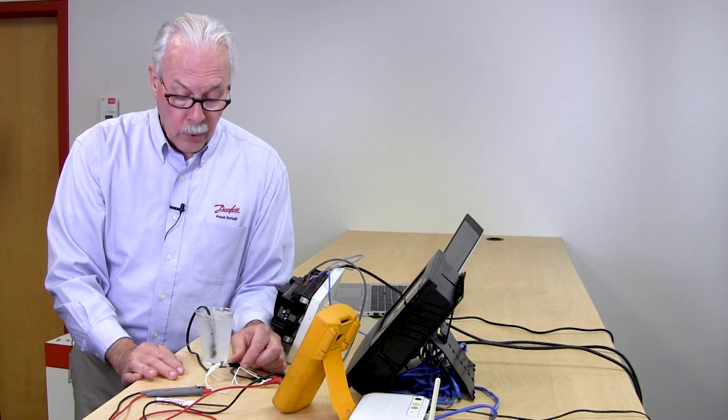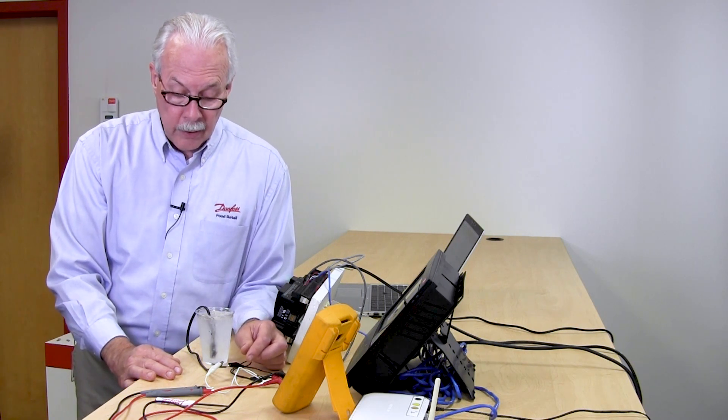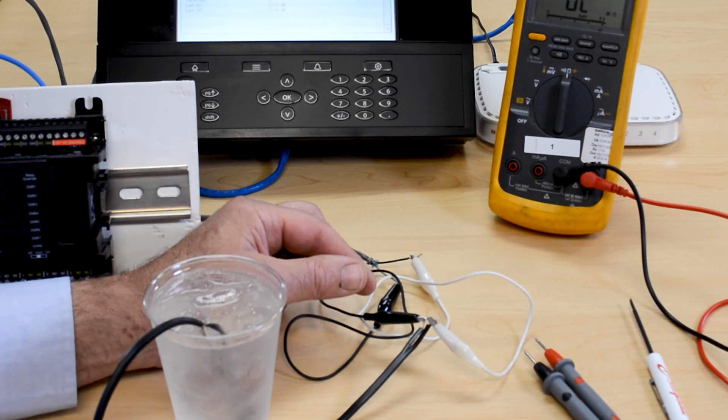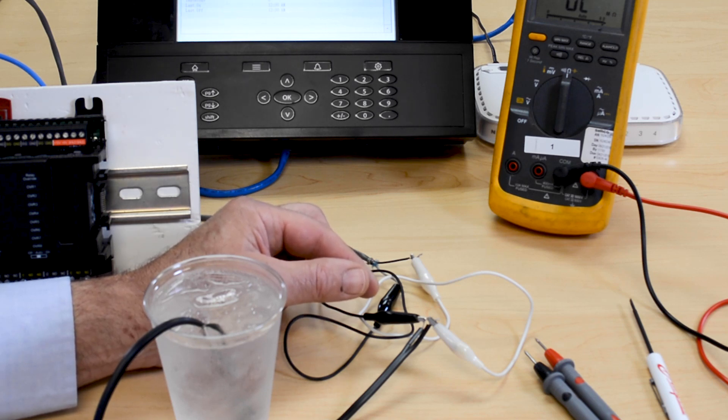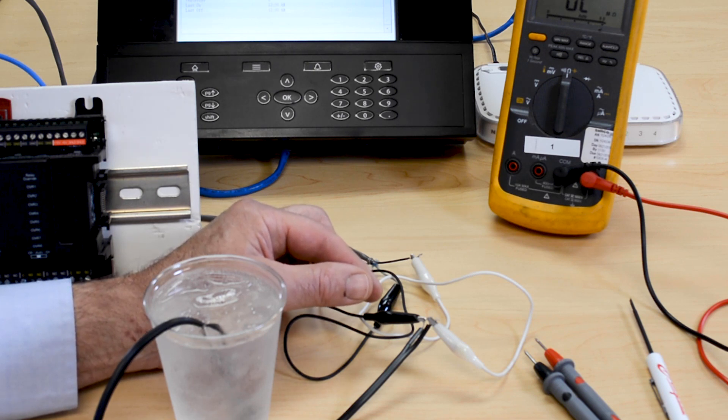We're now down on the floor and we're going to further evaluate or troubleshoot this problem. We're not going to go to where the sensor is inside the case. We're going to go to where the wires are connected to the cable returning to the I.O. or back up to the motor room.